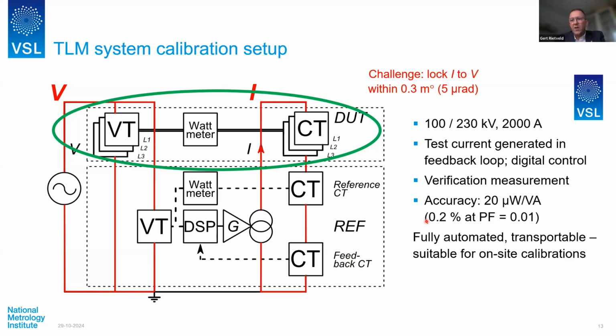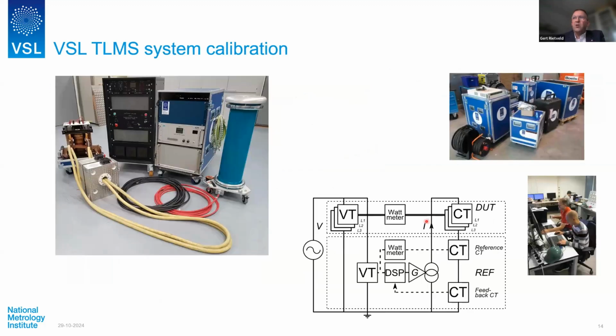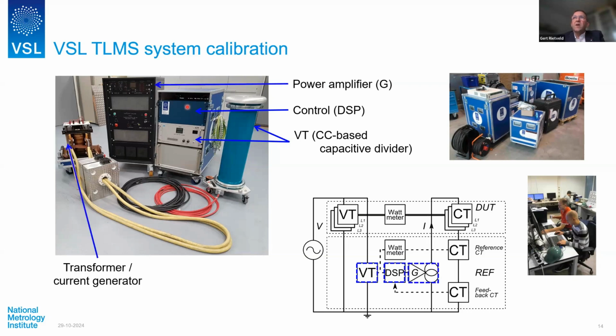And the advantage of the sampling approach is that it can be fully automated. So once we've set a current and a voltage, we can automatically adjust phase angle and do the calibrations. Really helpful in speeding up the calibrations. So how does the system look? This is a picture of the components. First of all, the voltage channel: a high voltage capacitor with low voltage electronics. The intelligence is in FPGA software in the NI digitizers. We have the power amplifier and the current transformer to generate the high currents.